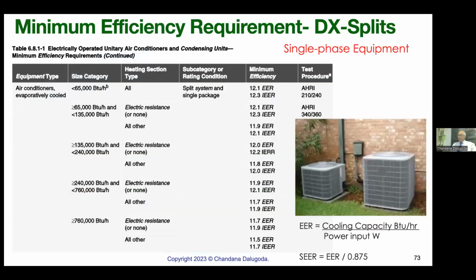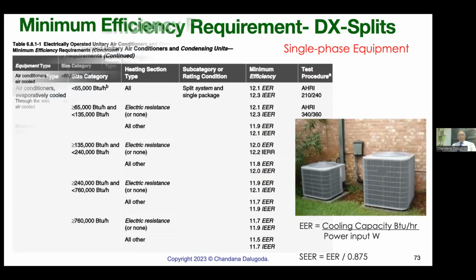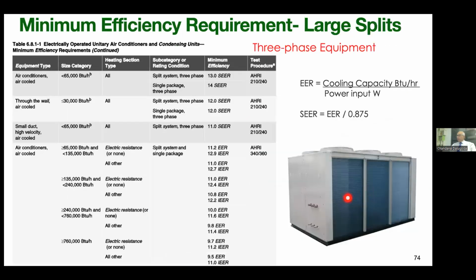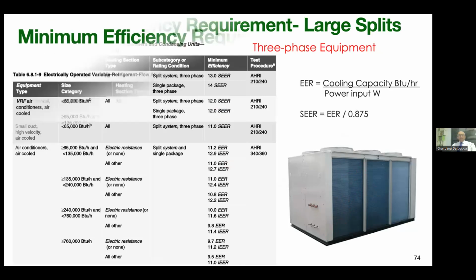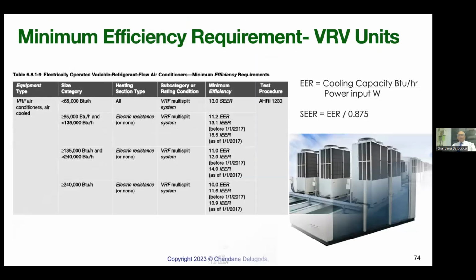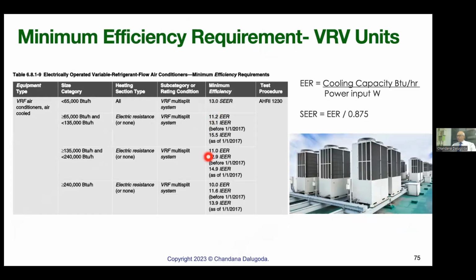So coming back to energy efficiency equipment, the energy efficiency ratio is given for single phase split units. Very, very tight energy efficiency values are given: 12.1 for 65,000 and below, these are the latest. And for large three-phase air conditioners with a large condensing unit, we have given the values. VRV values are again given, 11.2, 13.